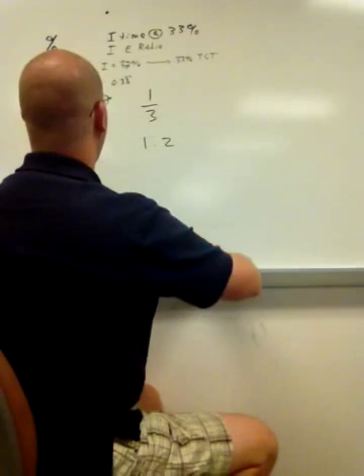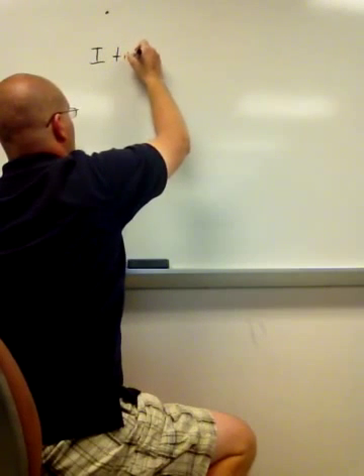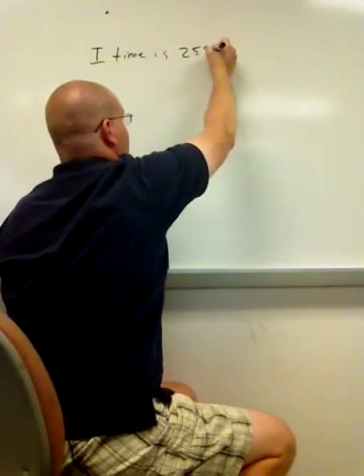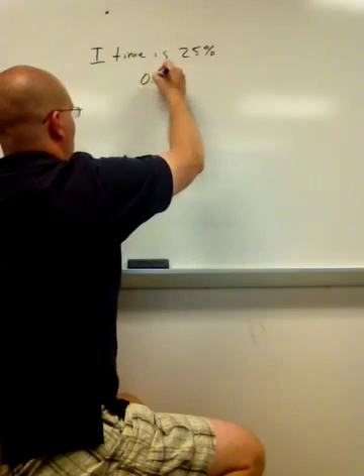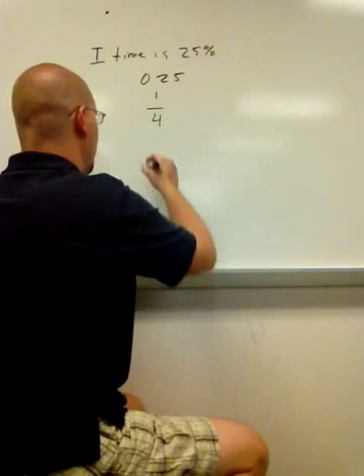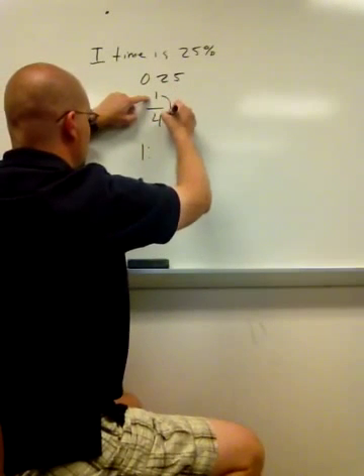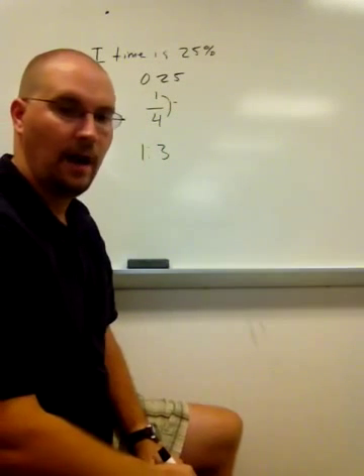Let's try it with another percentage. Let's say that my I time is 25%. So the decimal of 25 is 0.25, which is 1/4. That gives me an I to E ratio of 1 to, 4 subtract 1 is 3, 1 to 3 I to E ratio.